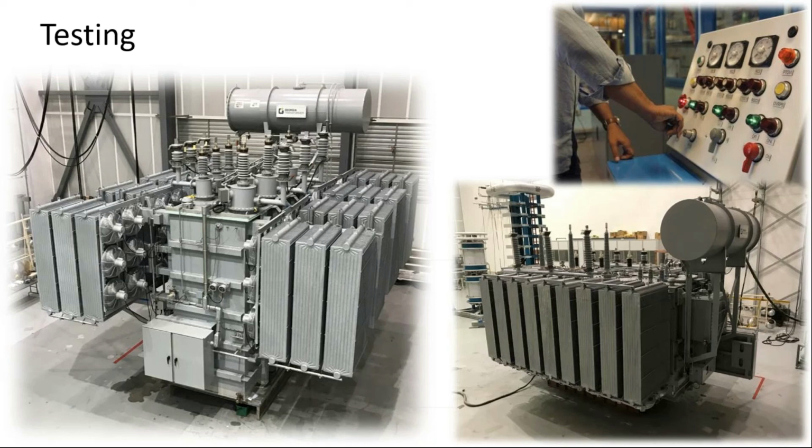There is the possibility of using a tail resistor which is outside. So that actually is a challenge. Getting the wave shape on HV may not be of any concern to LV. Otherwise, GSU testing is pretty much standard as a two-winding transformer. It might take a longer time for temperature rise tests because the leads carry heavy current, and the shorting for the LV becomes a challenge again.